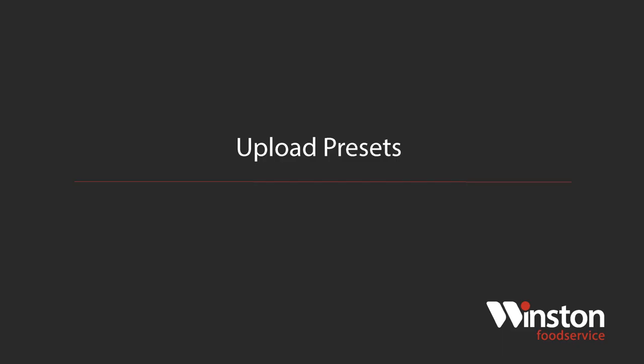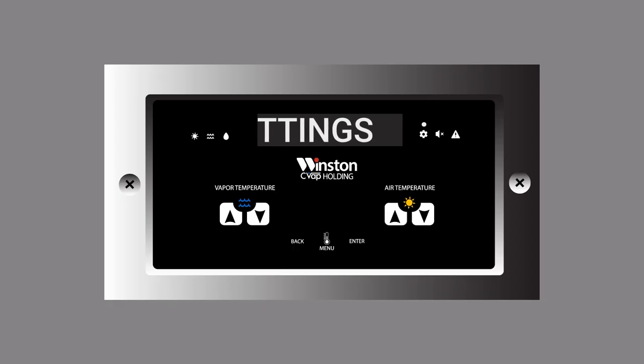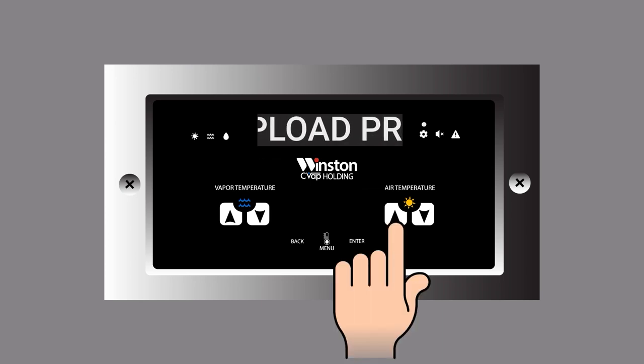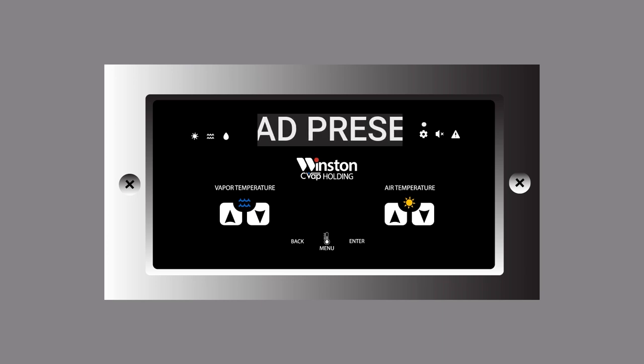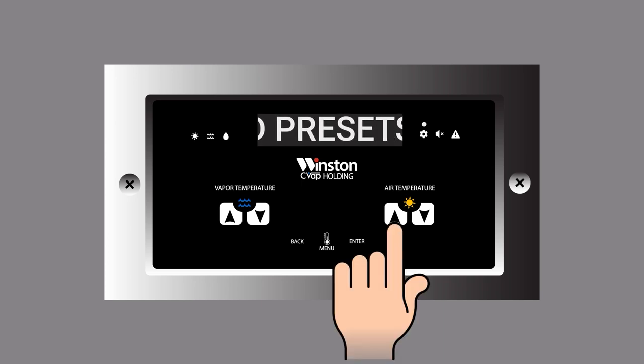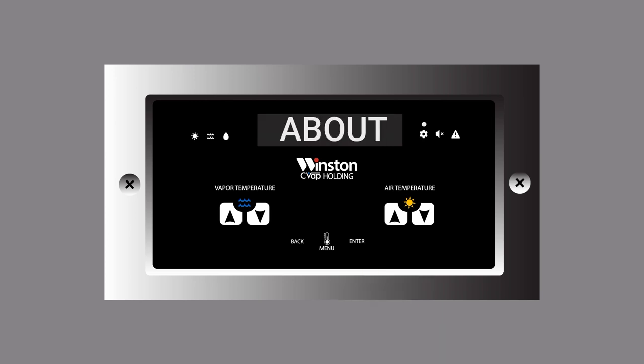Upload presets. With settings displayed, press the air temperature up button and Upload presets will be displayed. Upload presets does not apply to the drawer unit. About. With Upload presets displayed, press the air temperature up button and About will be displayed. Select Enter. The current loaded firmware version will be displayed. Select Back and About will be displayed.